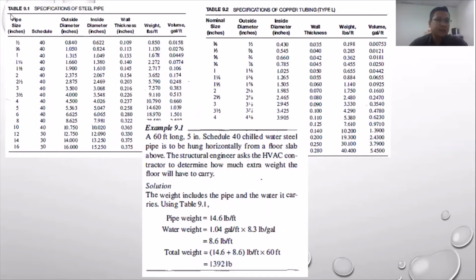But before that, I introduced what the content in the table 9. Okay, we have the pipe size, schedule, outside diameter, inside diameter, wall thickness, and weight in the British unit, and lastly the volume that can be carried by the pipe. We go first: how to check the size in the half inch. If we refer to schedule 40 in the half inch, it means the outside diameter is 0.8 something, and the inside is 0.6 something, and the thickness is automatically the difference between inside and outside. The weight is also reported here in the table.